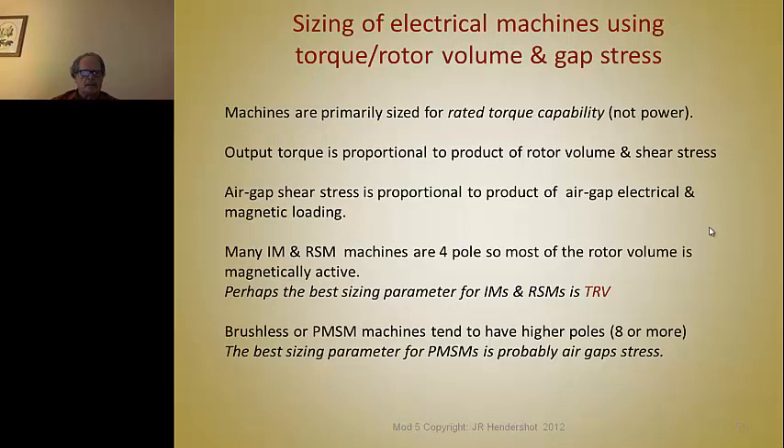The output torque is proportional to the product of the rotor volume and the shear stress. We'll look at a slide in a minute to see what shear stress is. Air gap stress is proportional to the product of the air gap electrical and magnetic loading — the electrical loading is the current loading and the magnetic loading is the flux loading. Many induction motors and reluctance synchronous motors are four-pole machines, so most of the rotor volume is magnetically active. The only part that isn't magnetically active in a four-pole machine is the shaft itself. So one could rate motors based on torque as a function of the rotor volume — that is, how hard you're working the machine.